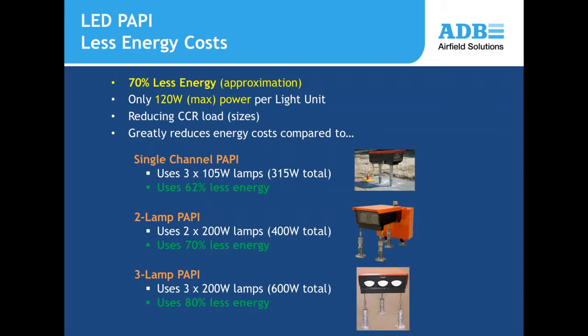A major advantage of the LED PAPI is energy efficiency. The LED PAPI uses 62% less energy compared to an ADB single-channel PAPI using 315-watt lamps. It requires 70% less energy versus a traditional two-lamp PAPI using two 200-watt lamps per unit, and 80% less energy compared to a three-lamp PAPI.